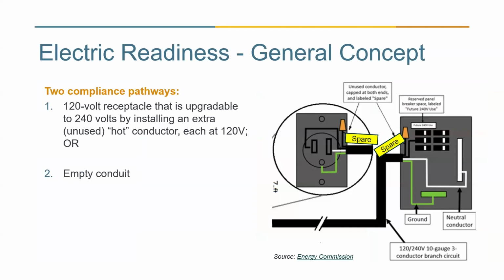So the general concept showing here on the right is that you either have the plug or the conductor connected via wiring to the panel. There's one live wire and then a spare wire that would be currently disconnected but could be connected in the future, which would allow the receptacle to be upgraded from a 120 volt receptacle to a 240. And the other option would just be an empty conduit through which wiring could be placed.